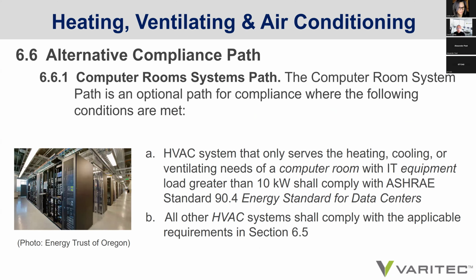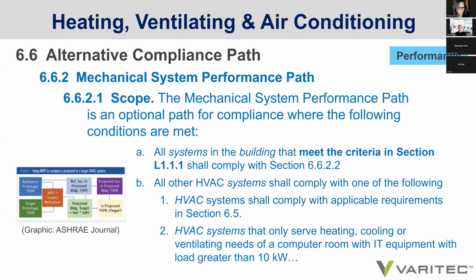There's now an alternative compliance path language available for computer rooms. An optional path can be used as defined in the standard under 6.6, and it goes on to say that an HVAC system that only serves the heating, cooling, or ventilating needs of a computer room with IT equipment load greater than 10 kW shall comply with ASHRAE Standard 90.4. All other HVAC sections shall comply with the applicable requirements of section 6.5.